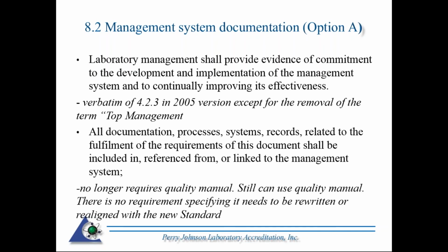So here I want to specify that there's no longer a requirement for a quality manual, but you can still use a quality manual. If you look at what's required under that bulleted item, and in your manual you have, say, that pyramid with a quality manual as a top tier document, then maybe internal procedures, technical procedures, forms, policies, things like that underneath of it, that will still comply with the requirements stated here. However, it's not required to have a quality manual.